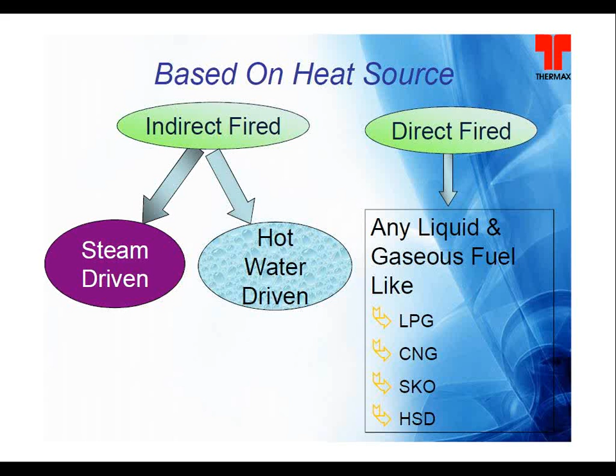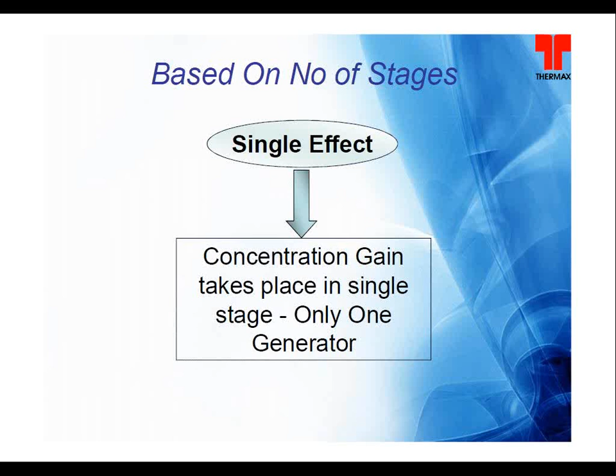Also, we can define it in terms of number of stages, like single effect and double effect. In single effect, the concentration gain of lithium bromide happens in only one stage, that is in one generator itself. That is the reason it is termed as single effect cycle. Whereas in double effect, the concentration gain happens in two separate generators. The vapor coming out from the first generator is used as the heat source in the second generator, because of which the efficiency of the entire cycle improves.